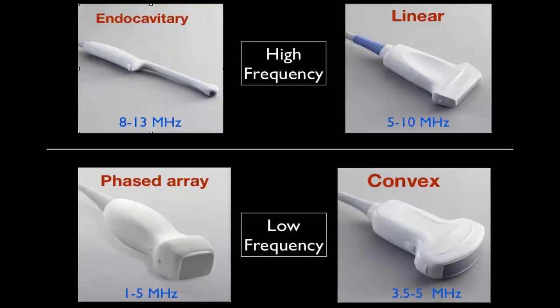We have high-frequency and low-frequency probes. The transvaginal and linear probes are both high-frequency, giving good resolution, but the downside is they do not provide deeper penetration into tissues. The phased array and convex probes are both low-frequency, excellent for deeper structures because of good penetration, but they will not give a higher resolution image for superficial structures.